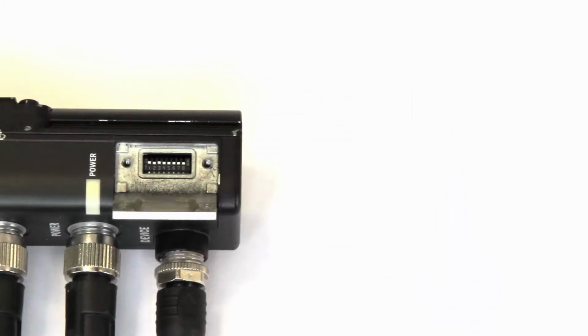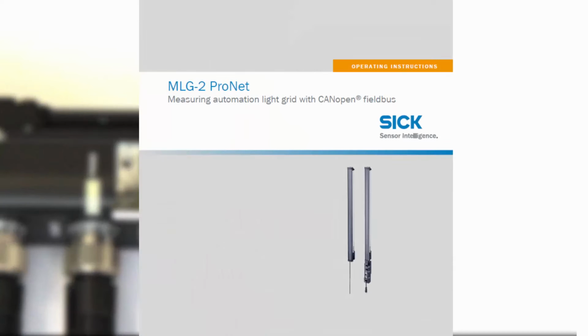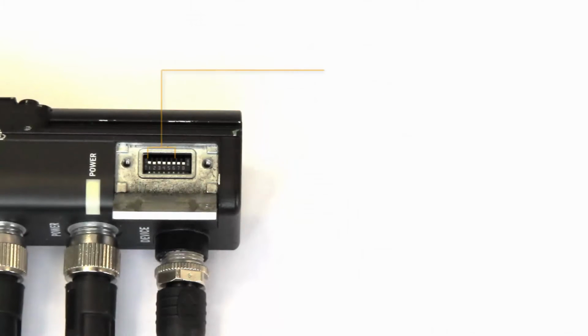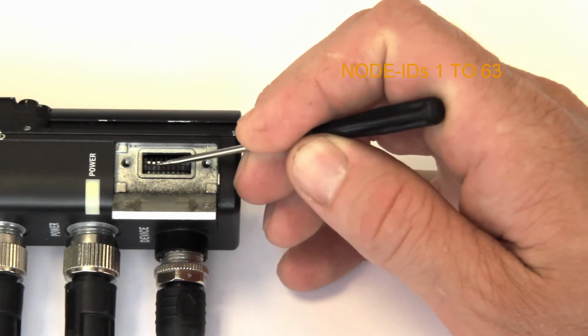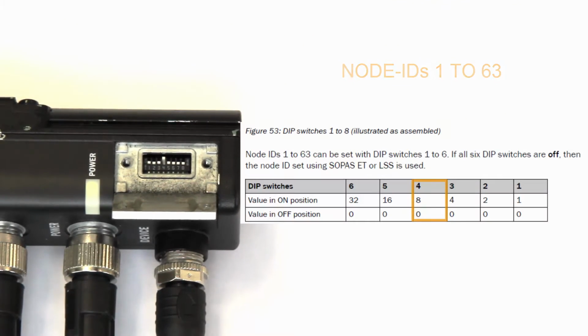The first step is to set the node ID directly at the device. The following information can be found in the operating instructions. By using the DIP switches from 1 to 6, the node IDs can be adjusted from 1 to 63. In our example, the DIP switch number 4 is activated, so the node ID is 8.